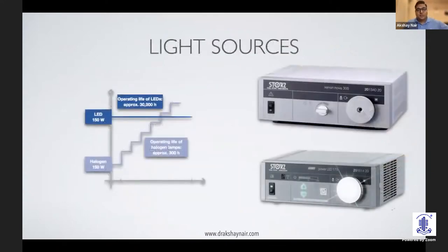And finally, your light source. When you talk about light source, there are two types. There is a halogen light source or the LED light source. Now, the halogen light source is cheaper. The life cycle, however, is much shorter. And you can see in this graph, the operating life for each lamp is about 300 hours. Whereas that for an LED is much more. So while your initial cost for the halogen may be lower, your recurring costs are much higher. So based on your usage or your expected usage in the future, make a choice on what you want to buy.